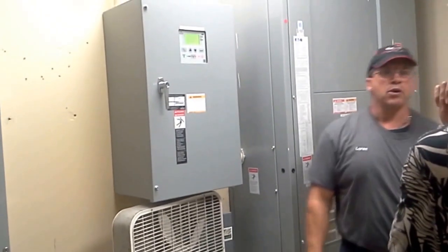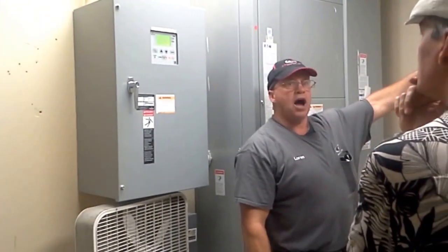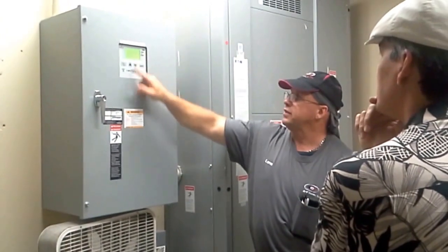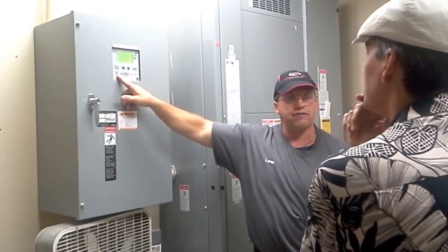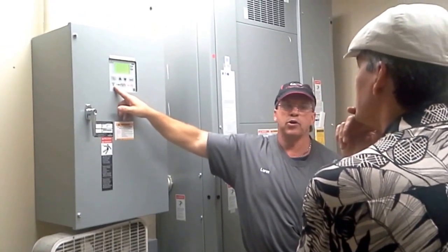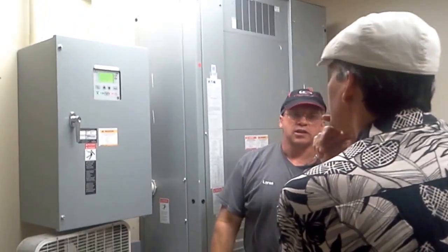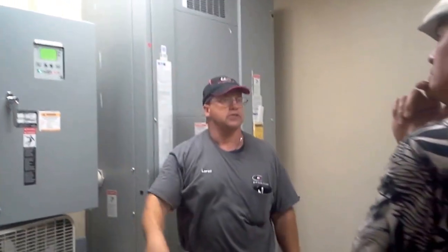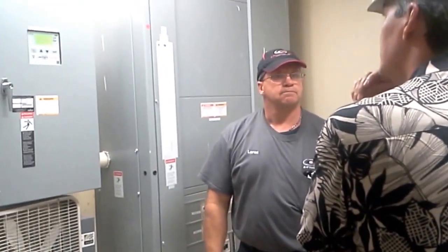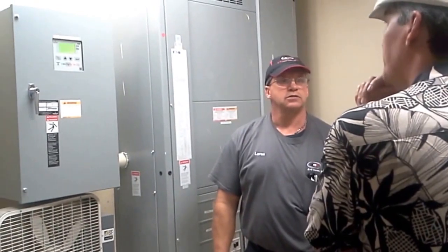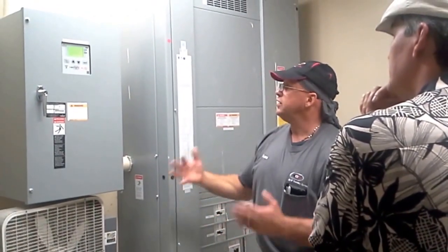If I went over there right now and I turned that generator off, it'll bypass that timer, it'll bypass the cool down time, everything, and it'll go to S1 or utility. It's default utility. If utility is there, I'm going. It's not going to leave you hanging until that clock is expired. It's fail safe. Any questions? No. You really don't have to do nothing to this. Everything is so automatic.